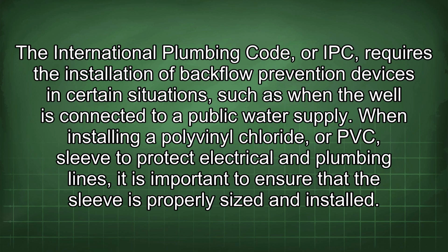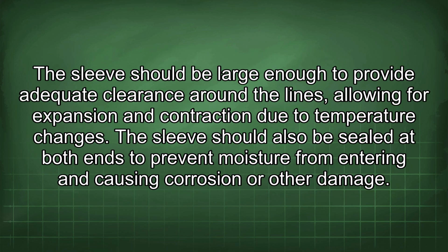When installing a polyvinyl chloride, or PVC, sleeve to protect electrical and plumbing lines, it is important to ensure that the sleeve is properly sized and installed. The sleeve should be large enough to provide adequate clearance around the lines, allowing for expansion and contraction due to temperature changes. The sleeve should also be sealed at both ends to prevent moisture from entering and causing corrosion or other damage.